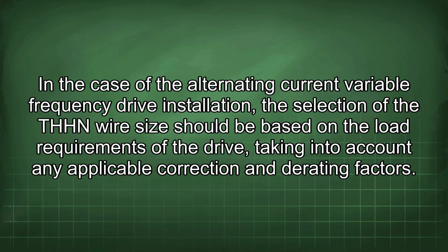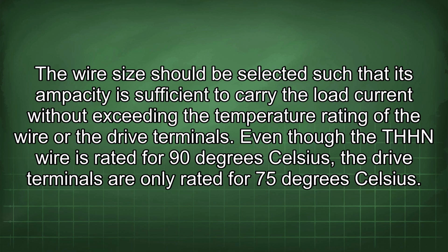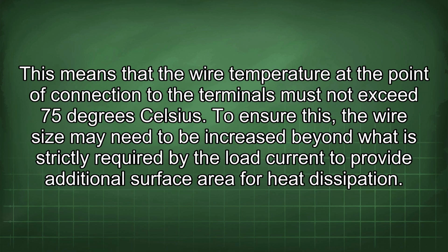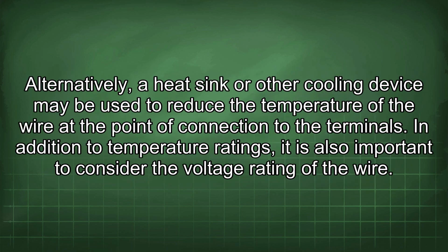In the case of the alternating current variable frequency drive installation, the selection of the THHN wire size should be based on the load requirements of the drive, taking into account any applicable correction and derating factors. The wire size should be selected such that its ampacity is sufficient to carry the load current without exceeding the temperature rating of the wire or the drive terminals. Even though the THHN wire is rated for 90 degrees Celsius, the drive terminals are only rated for 75 degrees Celsius. This means the wire temperature at the point of connection to the terminals must not exceed 75 degrees Celsius. To ensure this, the wire size may need to be increased beyond what is strictly required by the load current to provide additional surface area for heat dissipation. Alternatively, a heatsink or other cooling device may be used to reduce the temperature of the wire at the point of connection to the terminals.